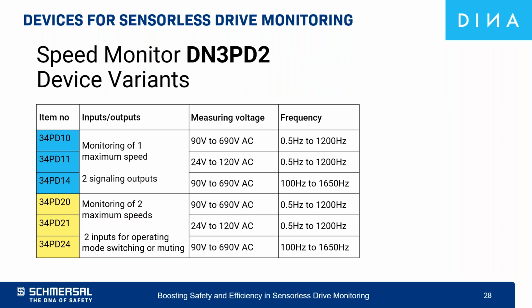And then both of these variants are available for different voltage ranges. So we have the standard voltage range from 90 volt to 690 volt AC. And then we have the low voltage range from 24 volts to 120 volts AC. And on top of that, these different variants are also usable for different frequency ranges. So we have the standard frequency range from 0.5 Hertz to 1200 Hertz, and the extended frequency range from 100 Hertz to 1650 Hertz. And all of this together, we come down to 6 device variants, taking into account all these different features.